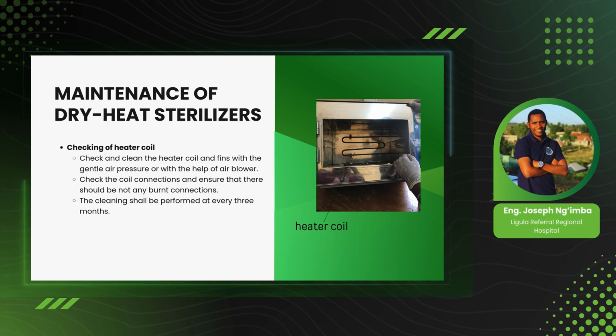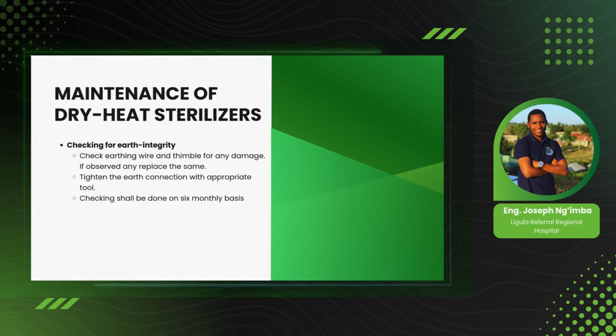Let's check another thing that we do on maintenance. The other thing we check is earth integrity. The importance of checking the earth integrity is to make sure that when you touch the machine surface, you don't feel any shock coming from the machine. If there is poor earth integrity, you feel some shocks coming from the surface of the machine once you touch it.